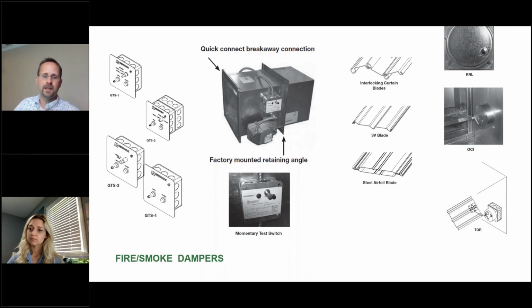So make sure you specify the proper blade type that you want in your specs. At minimum, I would say airfoil blades in every medium pressure system, and for low pressure, if cost is not a driving factor, I would probably go ahead and recommend that as well. But you can get the pressure drop data for all these to make that decision for yourself. There's a couple other options as well, such as resettable temperature links that can reset through the BAS or through the fire alarm system.